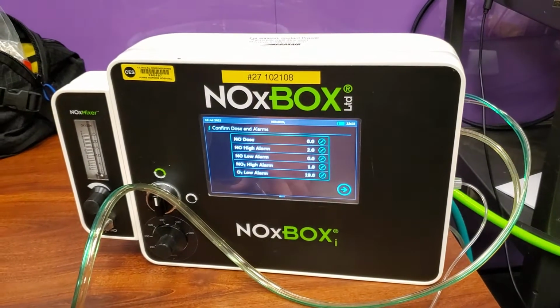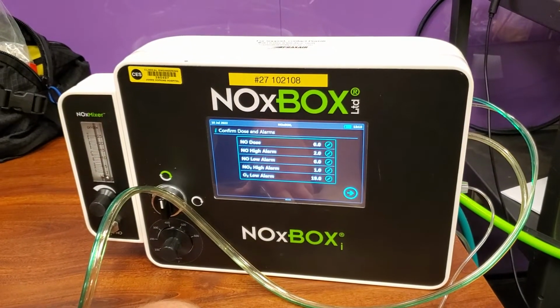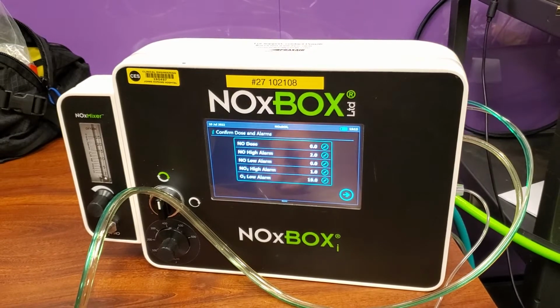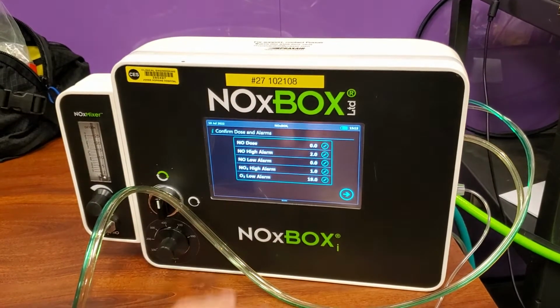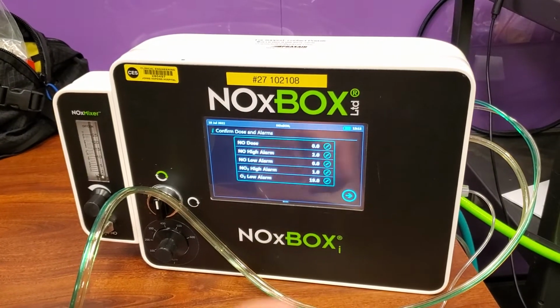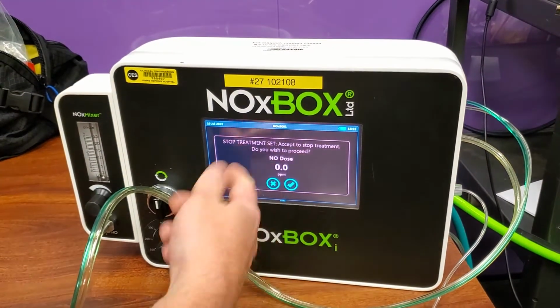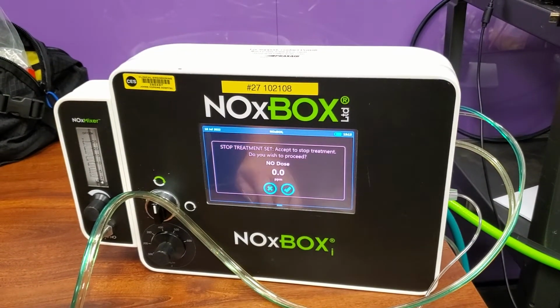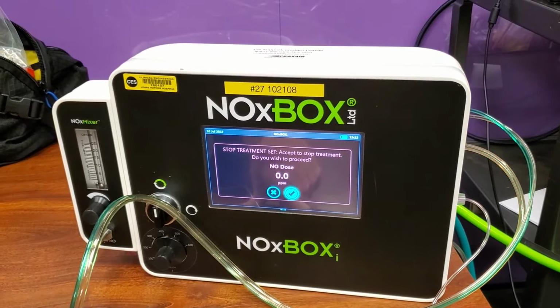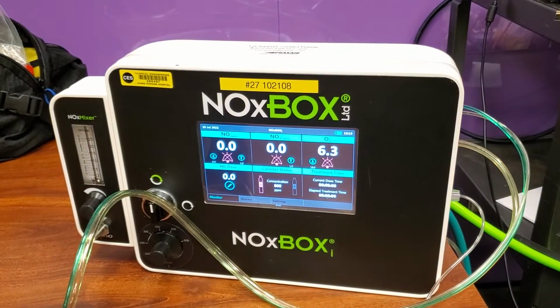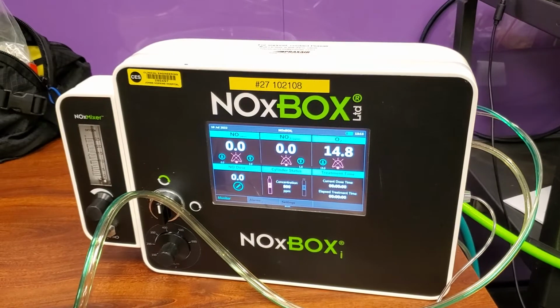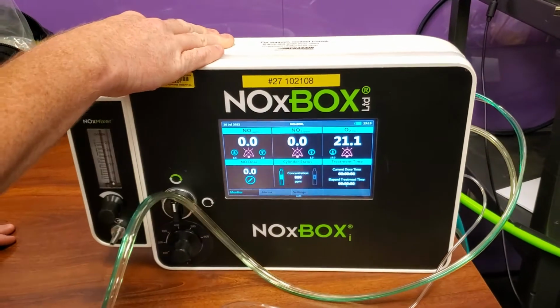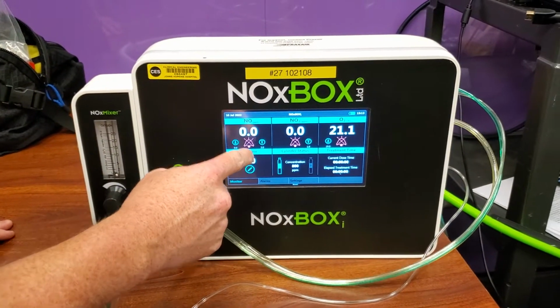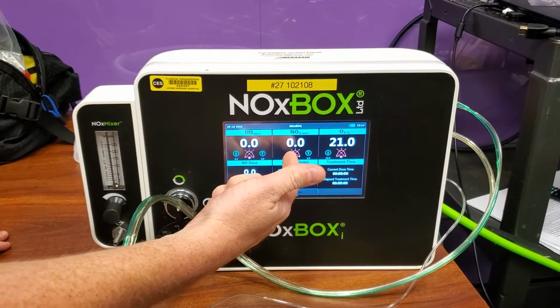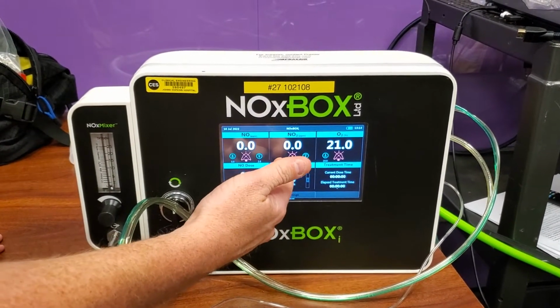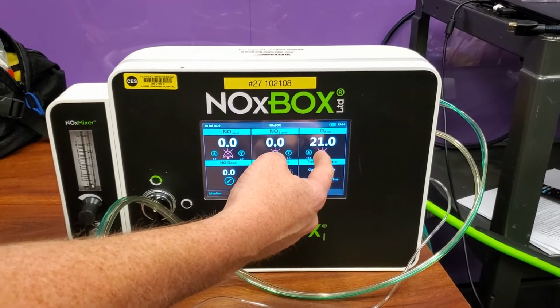And now it would allow you to select your alarms here. Obviously, our alarms don't matter at this point because we're not set on any dose. Every time that you change the dose, it will prompt you to confirm your alarms and make sure everything looks good there. So now it's obviously going to make us confirm that we do want to have no dose set. It's going to make a couple of little noises there. And so obviously, as we can see here on our main screen, our NO dose is currently set at 0. The patient's not receiving anything, so there's no nitrogen dioxide being sensed. And then this is the current FiO2 that it's seeing going through here.